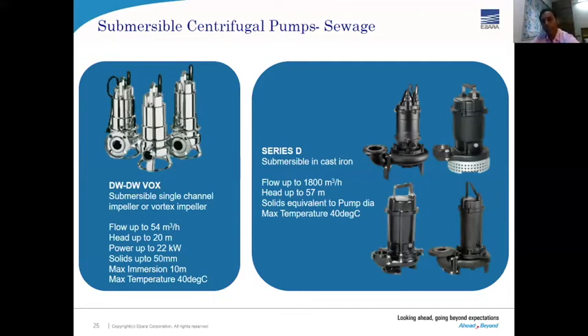Here we can offer the single channel non-clog, multi-channel non-clog, or grinder or cutter applications. Another feature is that we are offering the cutter pump with a flow of up to 135 meters per hour. This is quite a substantially bigger size, you can say. Here the motor is a four-pole motor driven pump, so the wear on the casing reduces. This is something you can look into when you have higher flow applications.